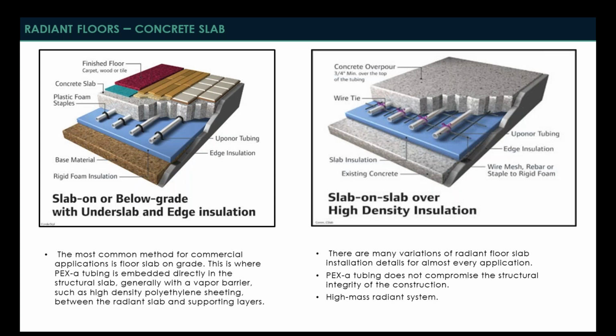So the first one I'd like to talk about are radiant floors, and specifically concrete slab radiant floors. These are typically found to be slab on grade, slab on below grade, or potentially a slab on slab application. And that's the most common method that you're going to see for commercial radiant floor concrete slabs. Essentially, the way that these work is the PEX tubing is poured directly into the slab. There's a lot that goes into the construction to make this work.